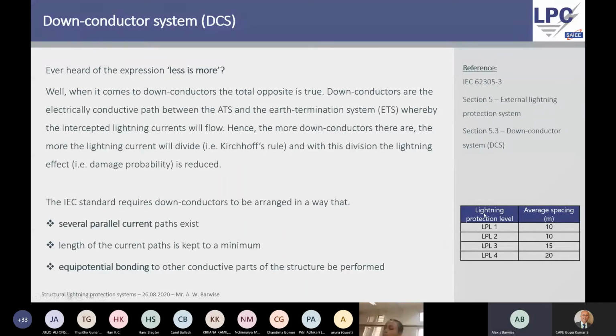Here we see on the table, right bottom, the lightning protection levels again, 1 to 4. And the standard gives us an average spacing which should be considered, or at least one has to try and obtain these average spacings between down conductors all along the perimeter of the building. It's definitely not always possible to get to that 10 value. Sometimes we are sitting with 12 or with 9, but the concept is such that we want to ensure multiple paths at a certain average spacing across the building.